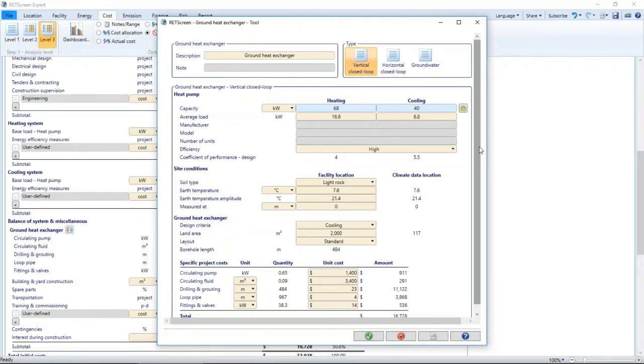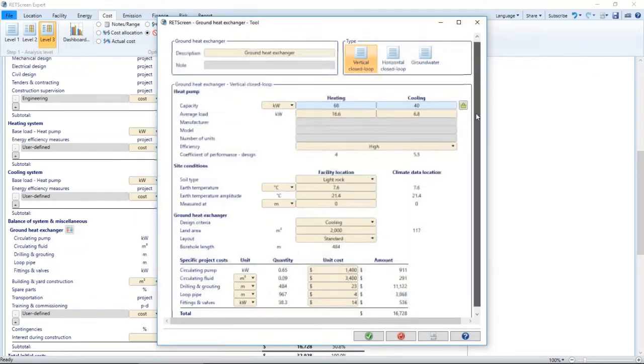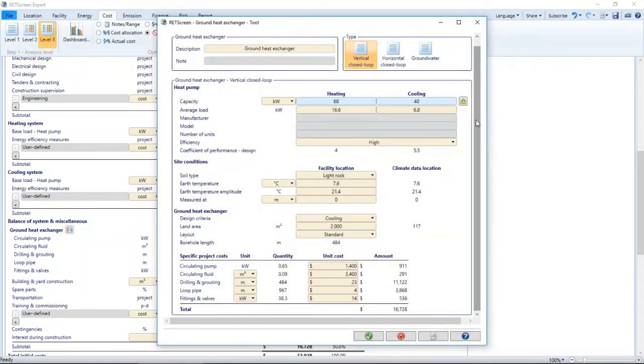The ground heat exchanger tool is used to help both size and cost the ground heat exchanger for a ground source heat pump system. 3 options are available: horizontal closed loop, vertical closed loop, and groundwater heat exchanger. To perform these calculations, some information is required: the heat pump capacity, the average load, and the site conditions. In this particular example, a vertical closed loop was chosen.